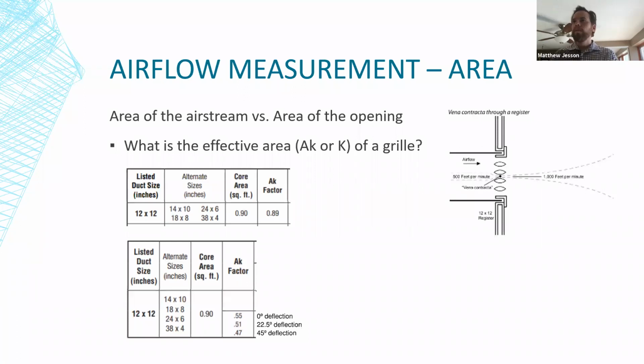So that effective area is the area of the airstream that we need to know. And for different grill manufacturers, you can look up some of these factors. I have two examples here, both from the same grill manufacturer, two different models of grills. The 12 by 12 in the first example has an AK factor of 0.89. So the effective area, the discharge of that grill, is 0.89 square feet. The one below has adjustable blades, so it shows you 3 different AK factors for 3 different deflection degrees.